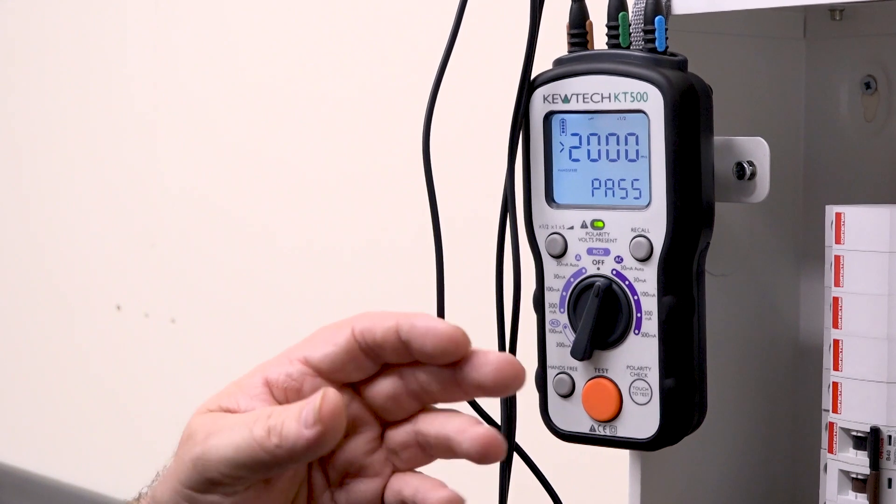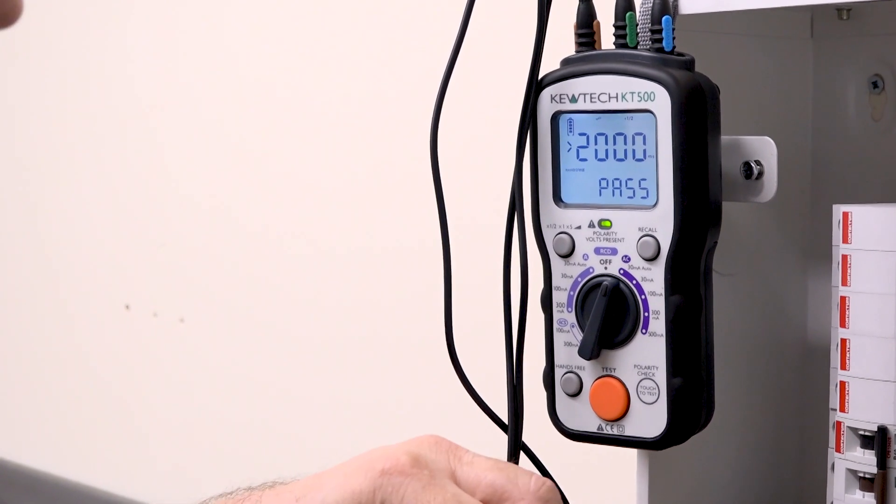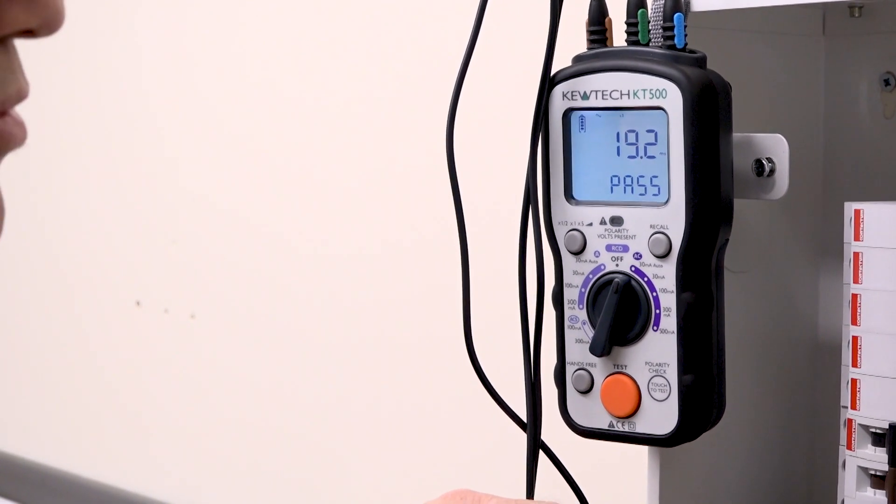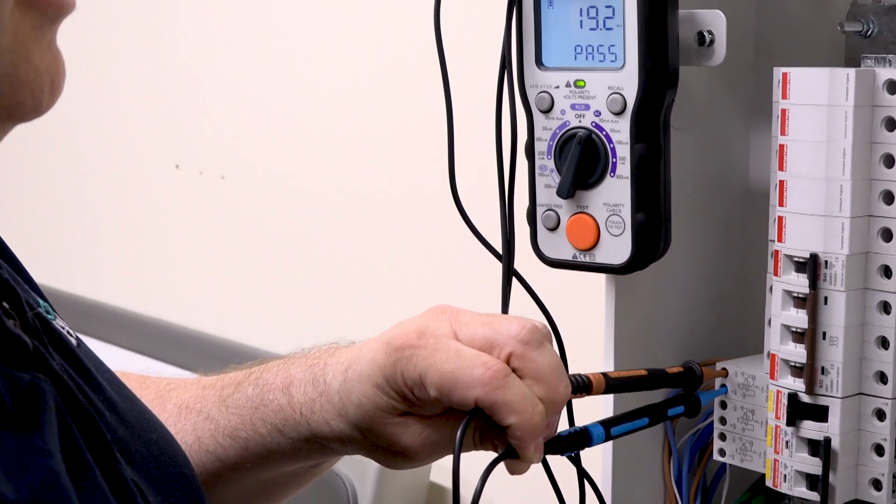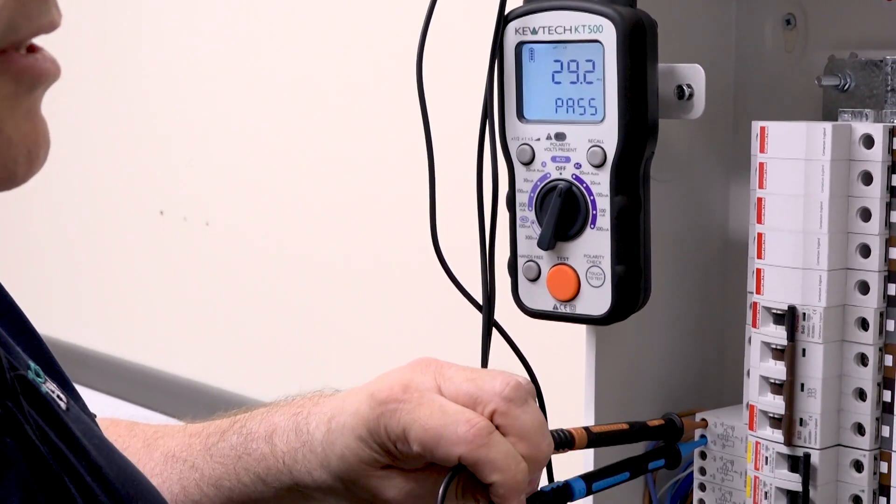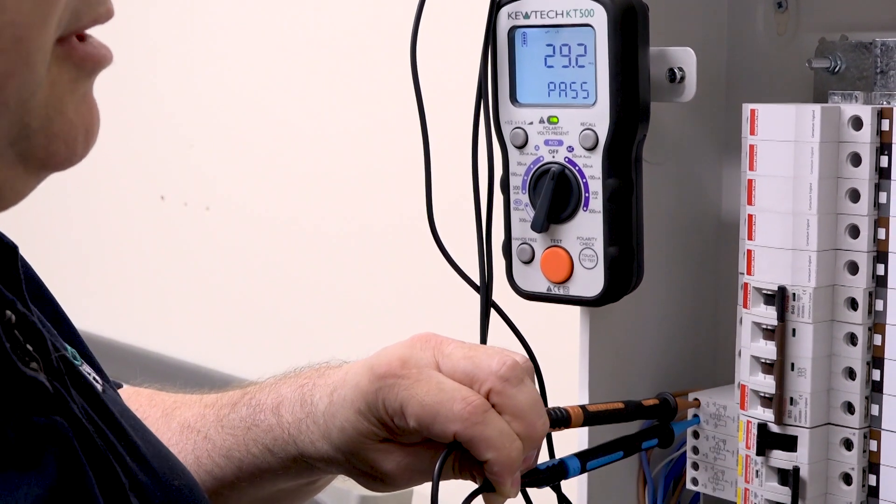...zero degrees, 180 degrees. And because it's a 30 milliamp, we'll do a times five for additional protection. So it's going through the sequence. There's the first one—it's tripped, so that's a times one. It's always best to give it two seconds, wait a couple of seconds before you reset it. So turn it back on.